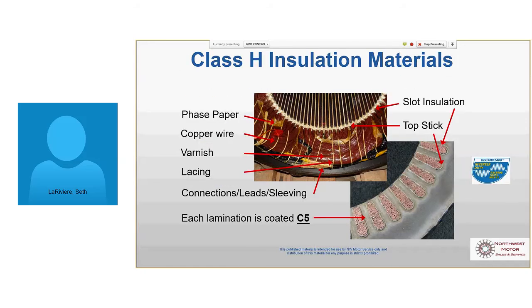Yeah. So the Stator is, and I had a slide, but I took it out unfortunately. I had to show a copy of the punchings, but this is the Stator here. These are all a bunch of thin laminations of steel, and punched into those is a design that's proprietary and unique to that manufacturer for that rating. You know, it affects the torque characteristics, the efficiency, the punchings.